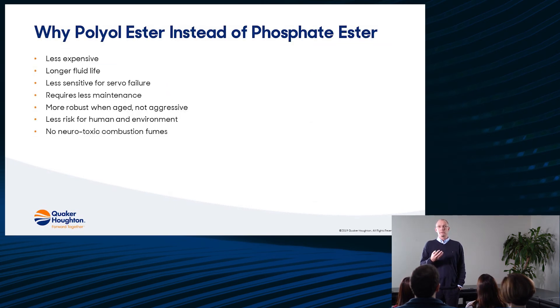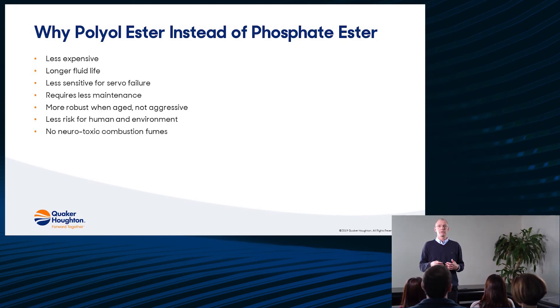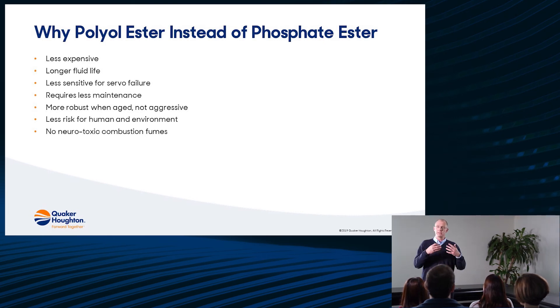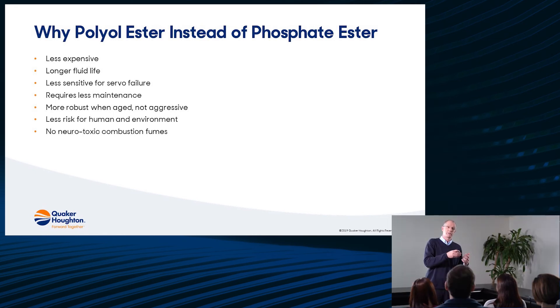Comparing polyol ester with a phosphate ester: polyol ester like Quintolubric is much cheaper to purchase, cheaper in use, less sensitive to failures caused by acidity or the high density of the phosphate ester, and less maintenance-sensitive. The aging products formed for polyol ester or Quintolubric 888 are not aggressive, and there is less risk for humans and the environment because the polyol ester is not CMR — not carcinogenic, not mutagenic, not reproductive. Last but not least, when it burns, phosphate ester produces a smoke which is neurotoxic.